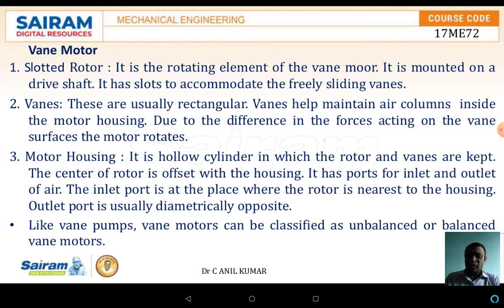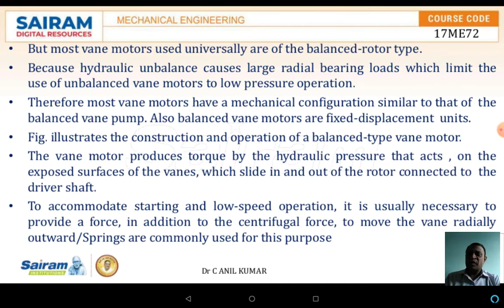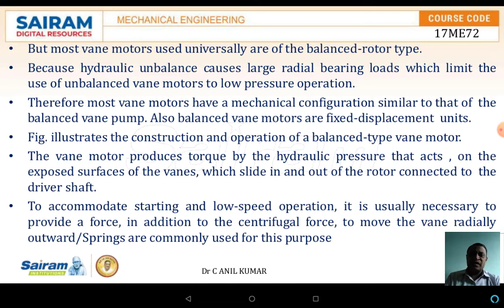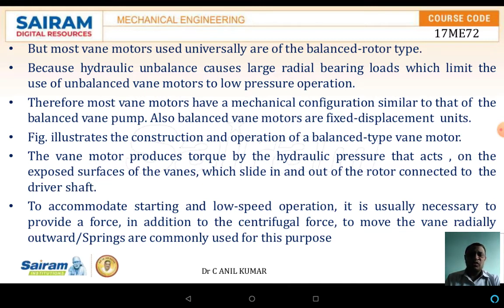Like the vane pump, the vane motor is also classified as the unbalanced type as well as the balanced vane motors. But most of the vane motors are universally the balanced rotor type only, because hydraulic unbalance causes large radial bearing loads which limits the use of the unbalanced vane motors in low pressure operations. Therefore, most of the vane motors have a mechanical configuration similar to that of the balanced vane pumps.